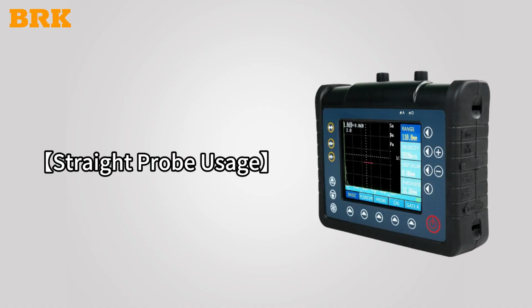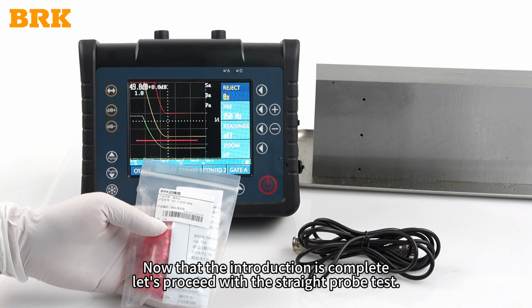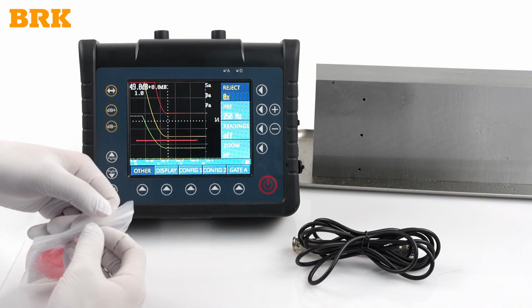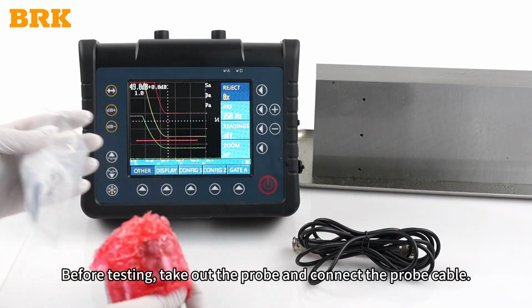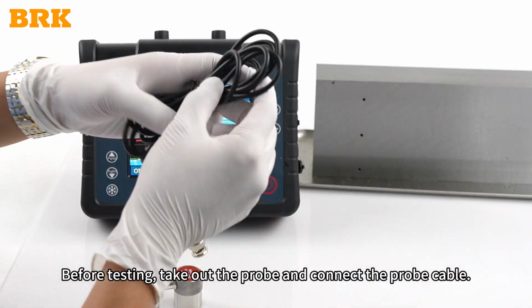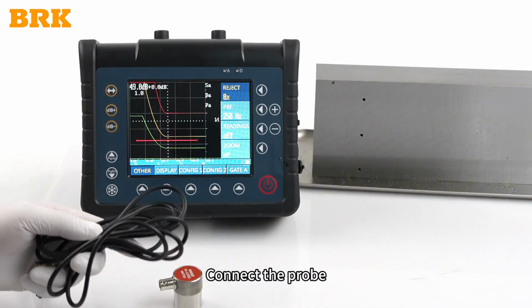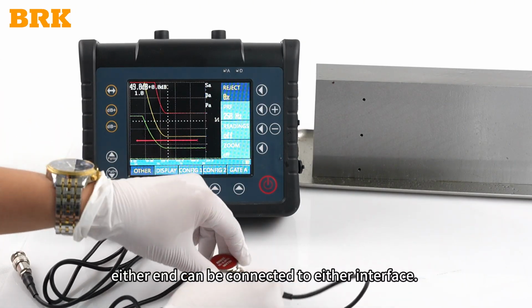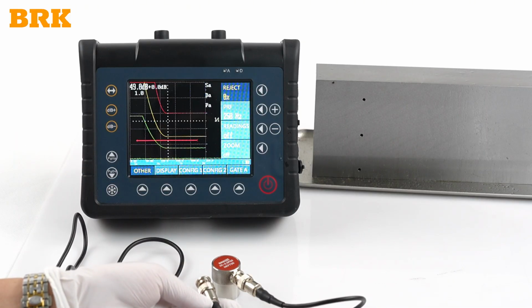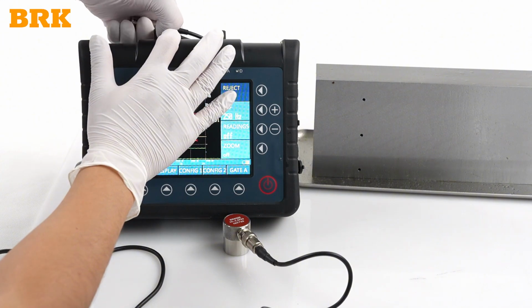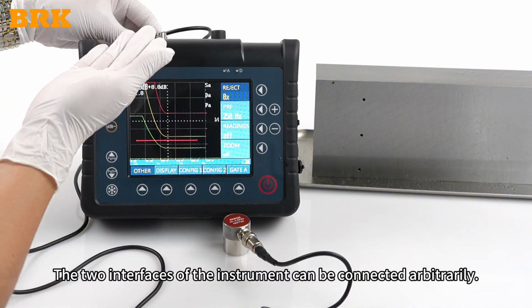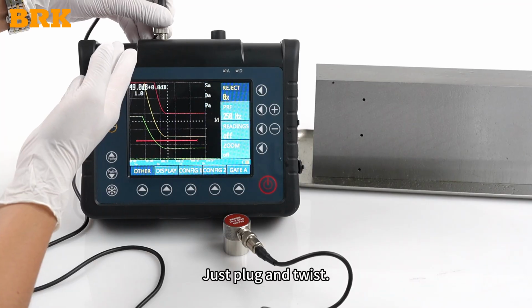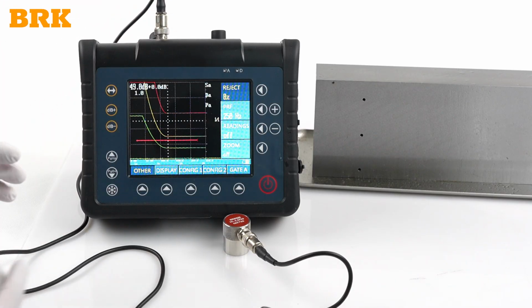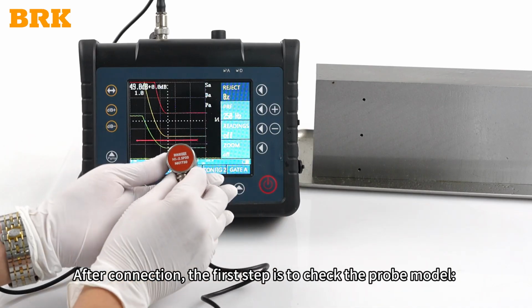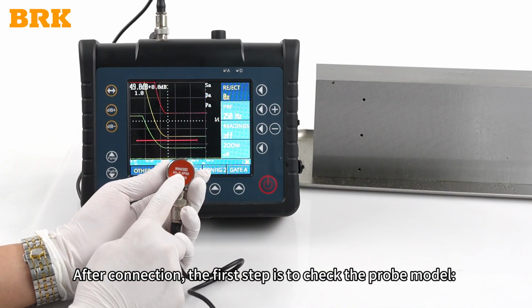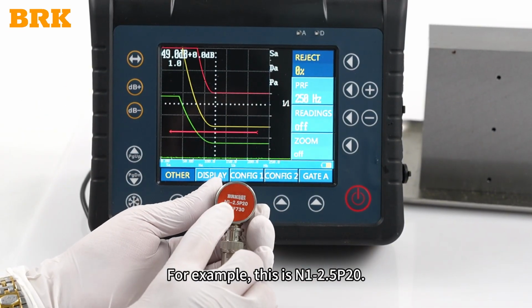Straight probe usage. Now that the introduction is complete, let's proceed with the straight probe test. Before testing, take out the probe and connect the probe cable. Connect the probe. Either end can be connected to either interface. The two interfaces of the instrument can be connected arbitrarily. Just plug and twist. After connection, the first step is to check the probe model. For example, this is N1-2.5P20.